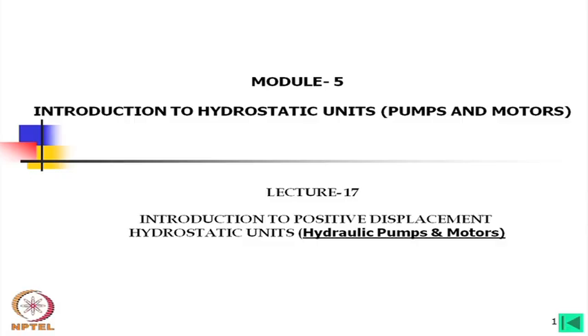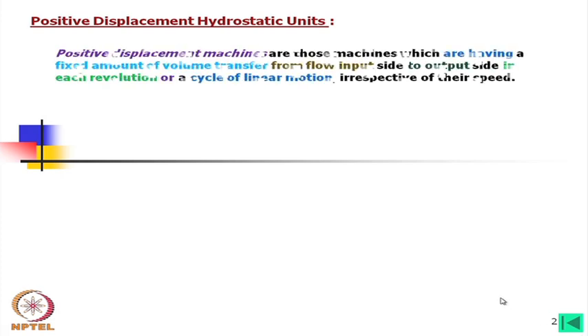Introduction to positive displacement hydrostatic units — hydraulic pumps and motors. Positive displacement machines are those which have a fixed amount of volume transfer from the input side to the output side in each revolution or cycle of linear motion, irrespective of their speed. Whatever the geometric displacement, the same amount is transferred from input to output side, whether in rotary machines or linear actuators.